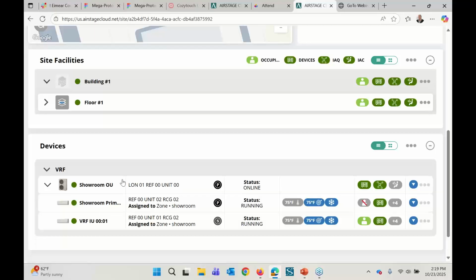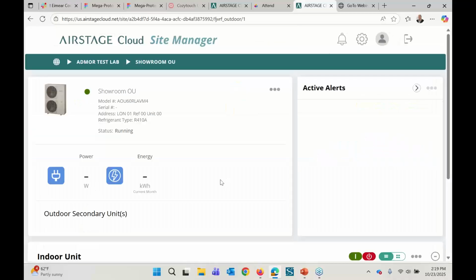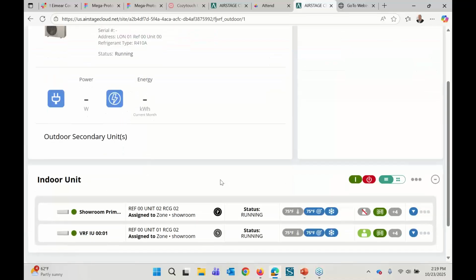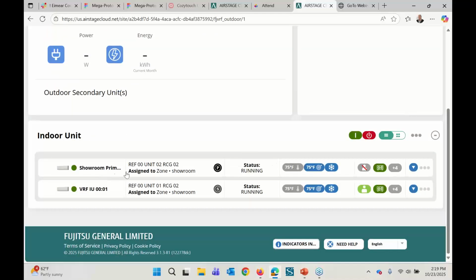The first thing we're going to do is go look at our site manager. The site manager is what allows us as engineers, contractors, and technical support people to come in and monitor and control the VRF system. When I come into my site manager, I can see that I've got two units right now - they're indoor units. You can see that one is a primary, one's a secondary unit, so the secondary unit is being driven by this top indoor unit. The first value you see is the actual space temperature, which is 75. The middle value is the set point. Because they're blue and you see the snowflake, it's in cooling.